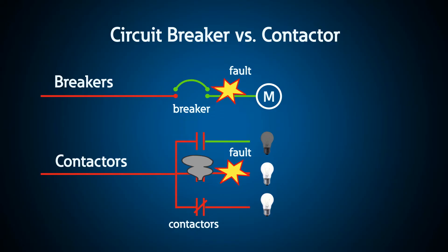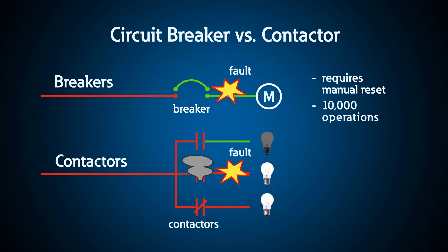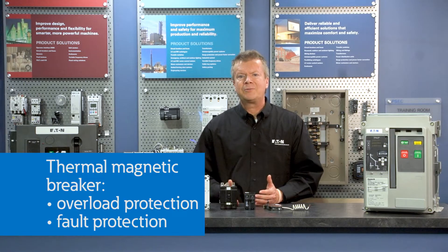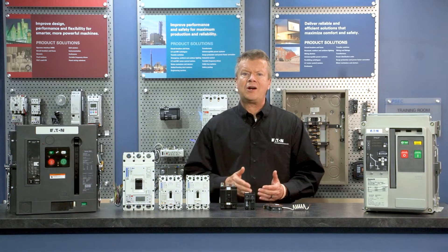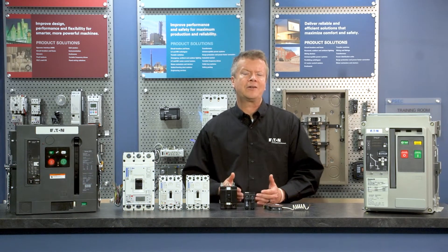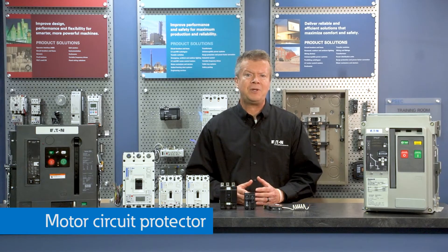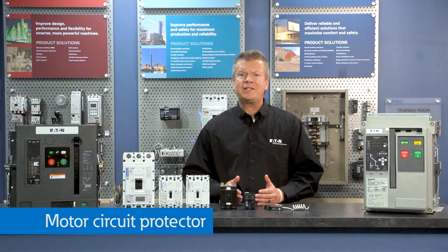Another significant difference is that while you can easily turn off a breaker electrically, manual intervention is often required for turning a breaker back on. Circuit breakers are typically designed for 10,000 operations and contactors are designed for a million — but since breakers aren't really intended for many on-off cycles, 10,000 operations is significantly more than would be required in their lifetime. A thermal magnetic breaker has both overload and fault protection. To give a contactor the same protection, it would require a thermal overload relay and a fault clearing device like a fuse or special protective device called an HMCP installed with it — this is typically the case in motor control buckets.